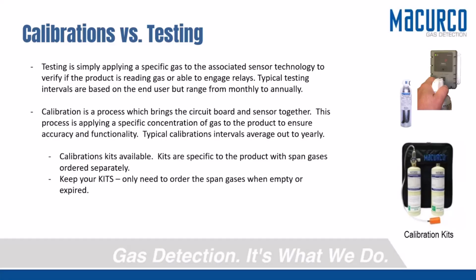A test is different. So a test is applying whatever concentration of gas to the detector to make it function. Meaning, if you're tied into a fan for ventilation purposes, or you're tied into the fire alarm for evacuation purposes, we can technically get those relays to trigger via test gas. And that test gas is, again, just applying gas to the detector, make it trigger its relays, and you move on. But a calibration is matching that sensor and that circuit board into one.